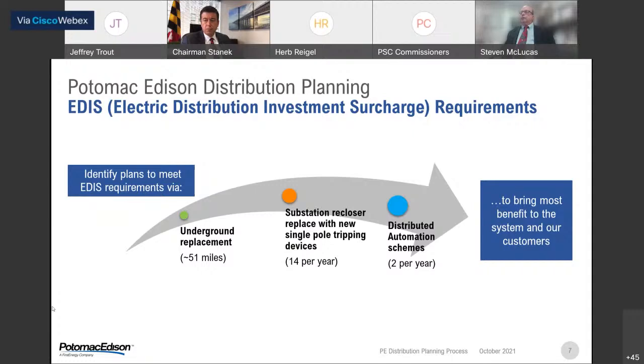And then I talked about distribution automation schemes. This is generally new technology for us; we've been doing it for four or five years now, I believe. What it does: we do work to tie circuits together, and then we put automated schemes out on the line so that if there is a fault or problem on the line, the reclosers on the line will function together, recognizing where the problem is.